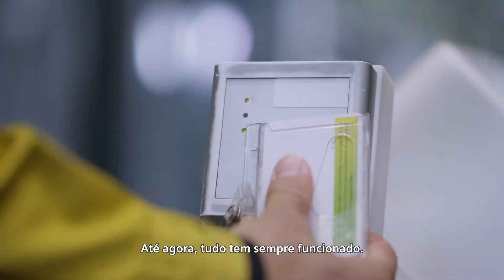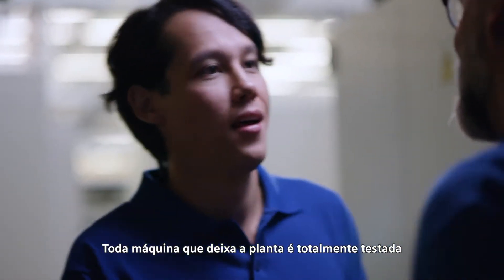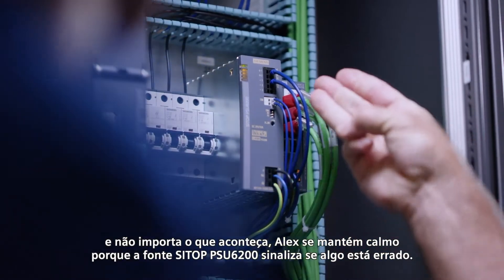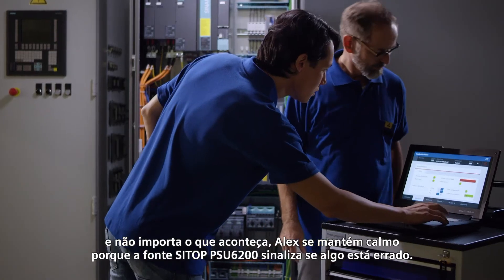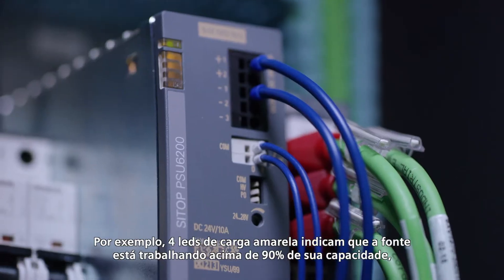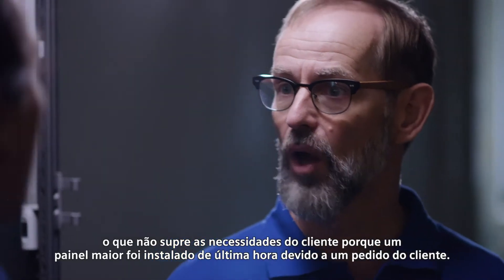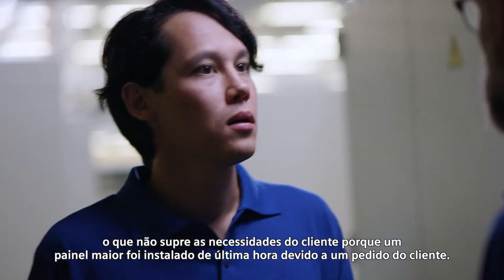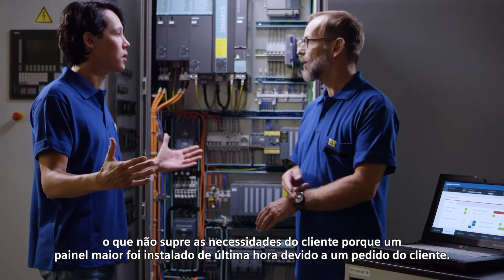So far, everything has always worked out. Every machine that leaves the plant is thoroughly tested. No matter what happens, Alex stays calm because the SITOP PSU6200 signals if something's wrong. For example, four yellow load LEDs indicate that the PSU is working at over 90% capacity, which is not in spec with his customers' requirements because a larger panel was installed on short notice due to a customer request.